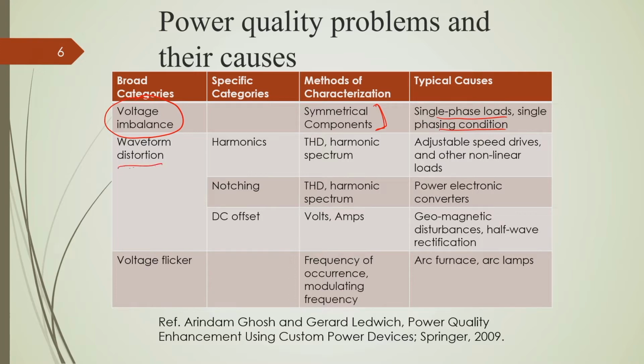Similarly, waveform distortion is another category of power quality problems. There are some subcategories, one of which is called harmonics. As I said, we will discuss harmonics in one of our slides. Harmonics are generated because of non-linear loads, and these are characterized with an index called THD, which stands for total harmonic distortion. It quantifies how much harmonic content we have, either in voltage or in current. Similarly, notching is another sort of waveform distortion. Harmonic is basically a periodic type of waveform distortion, and notching is a very short duration waveform distortion.